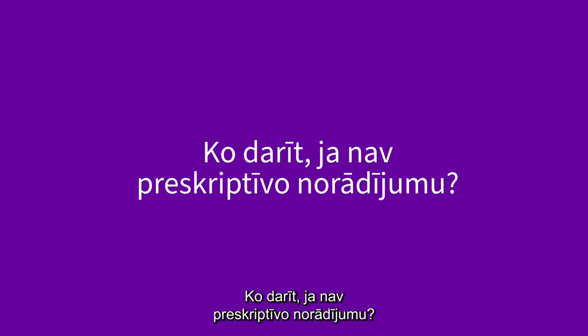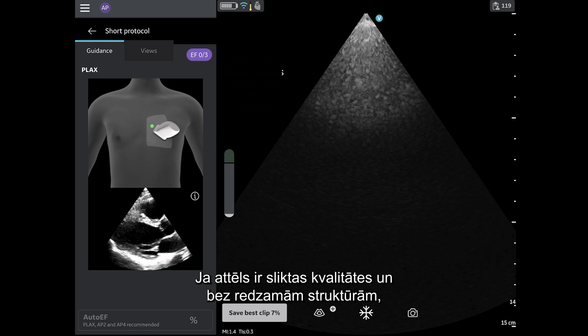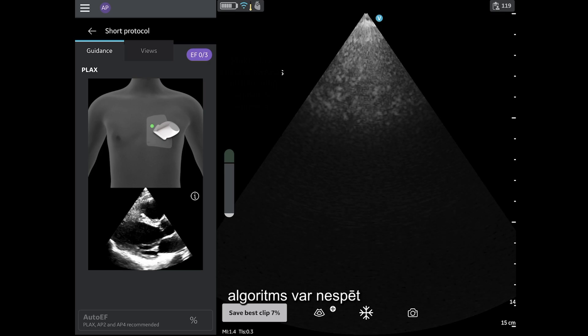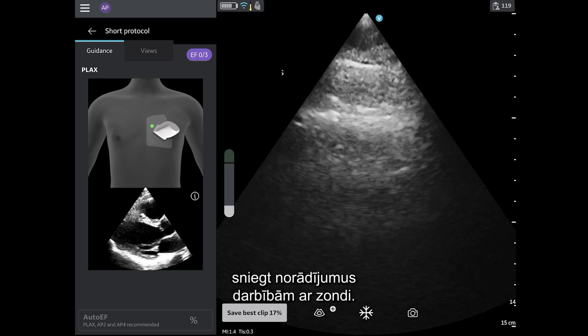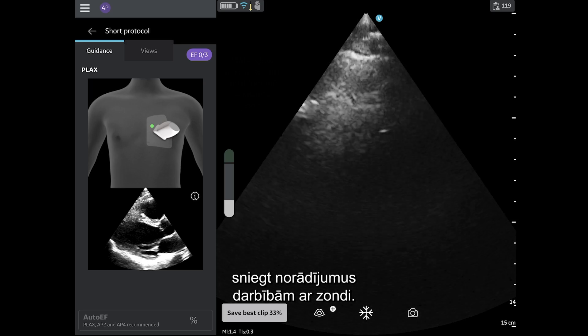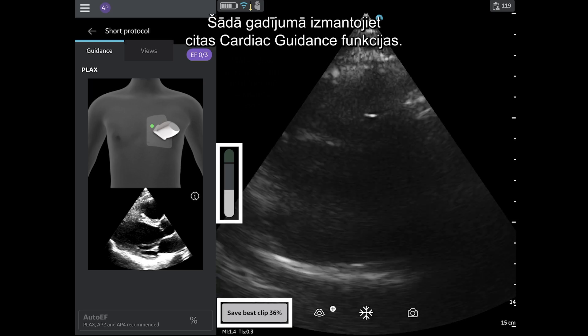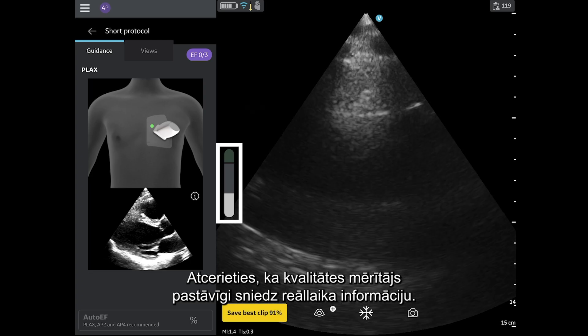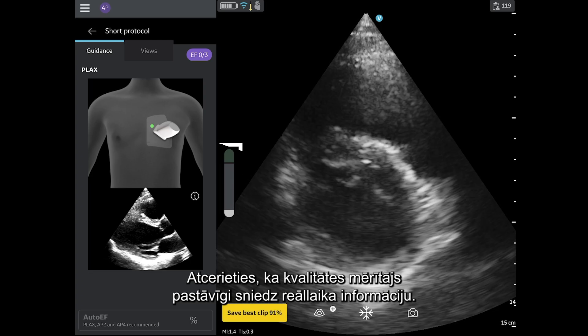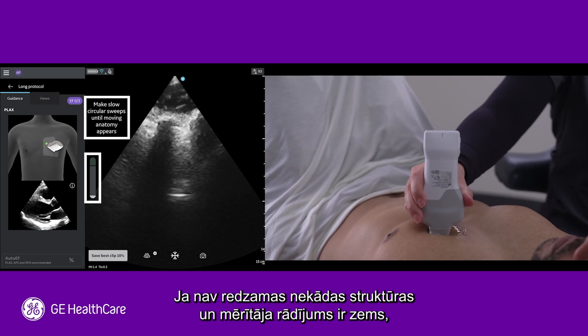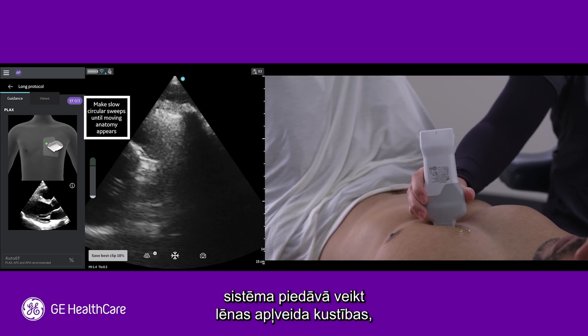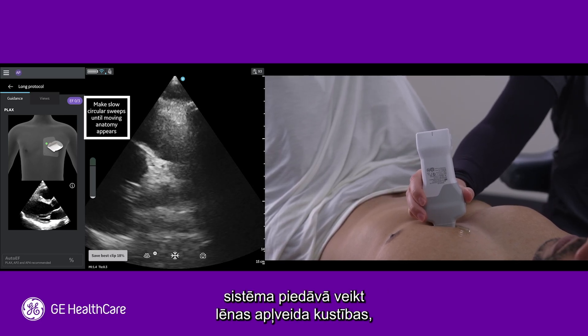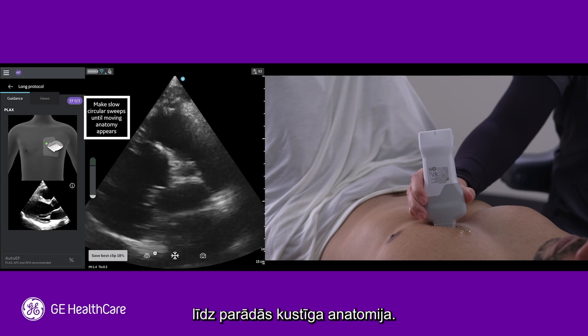What should I do if there is no prescriptive guidance? If the image is poor quality, without any structures visible, then the algorithm may not be able to provide any guidance for probe movements. In this scenario, rely on the other cardiac guidance features. Remember you always have continual, real-time feedback from the quality meter. When no structures are visible and the meter is low, the system will prompt you to make slow circular sweeps until moving anatomy appears.